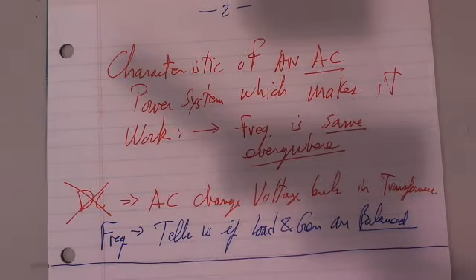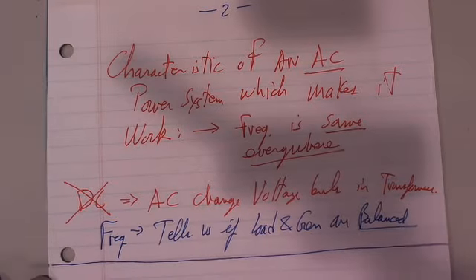So this means that we can use that frequency as the signal at every generator as to whether the generator should go up or down in its output. Okay, up or down in its output. So this allows us to control the generation very accurately.